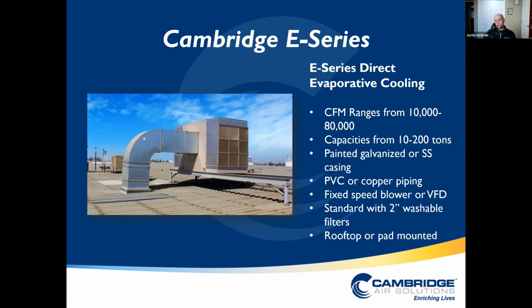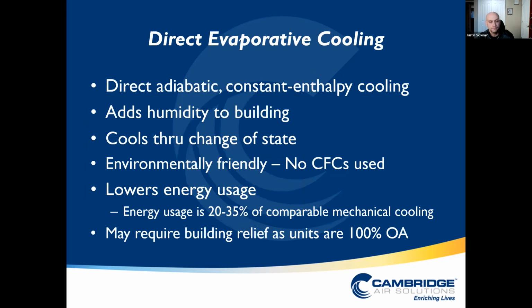What this is good for is replacing a large quantity of what we typically refer to as swamp coolers. So I was actually just on a building where we had 20 swamp coolers. They were difficult to maintain, difficult to modulate. There really is no control system. And so this person was looking at consolidating all 20 of those into one evaporative cooler. With one evaporative cooler, you get one piece of equipment, one set of controls, one set of maintenance requirements.